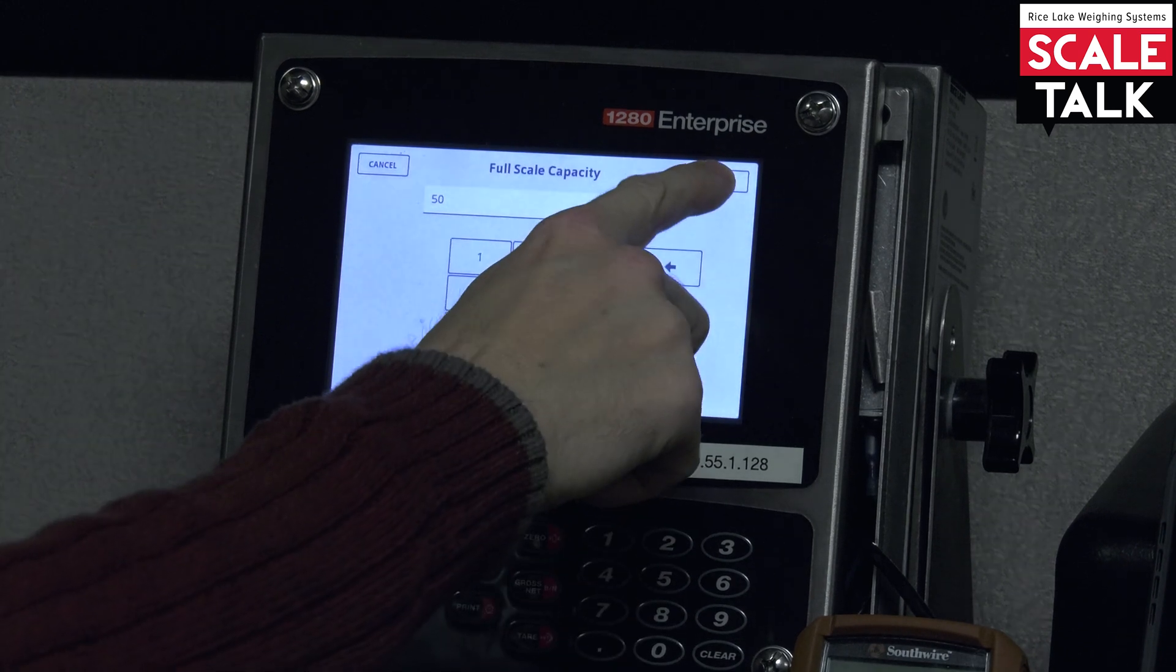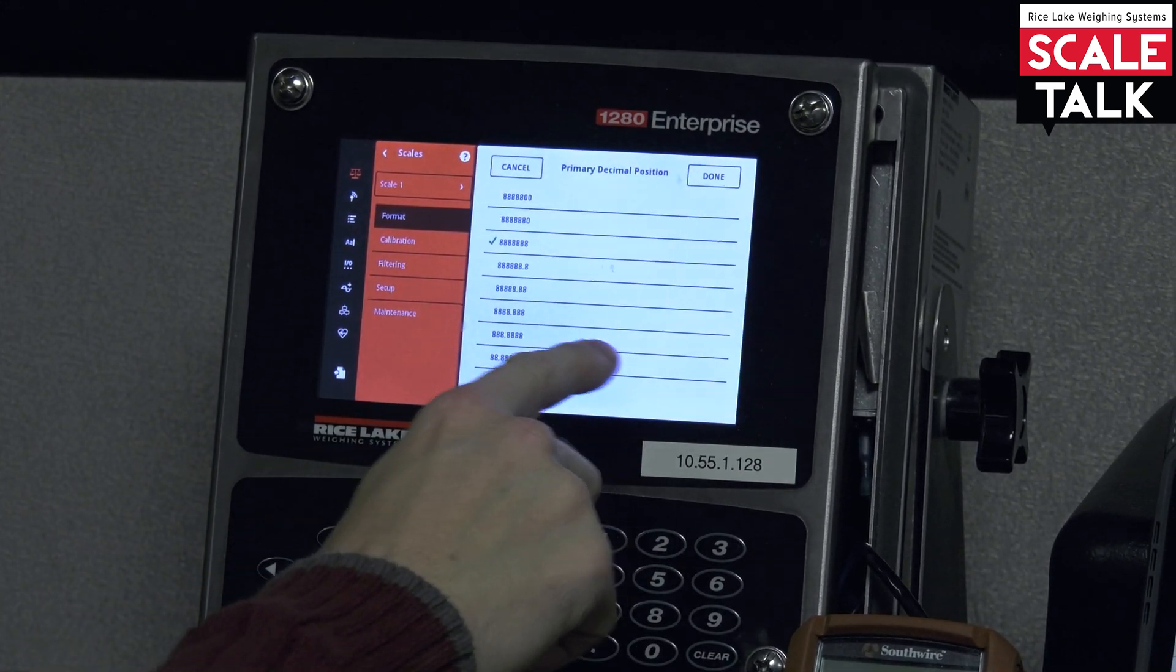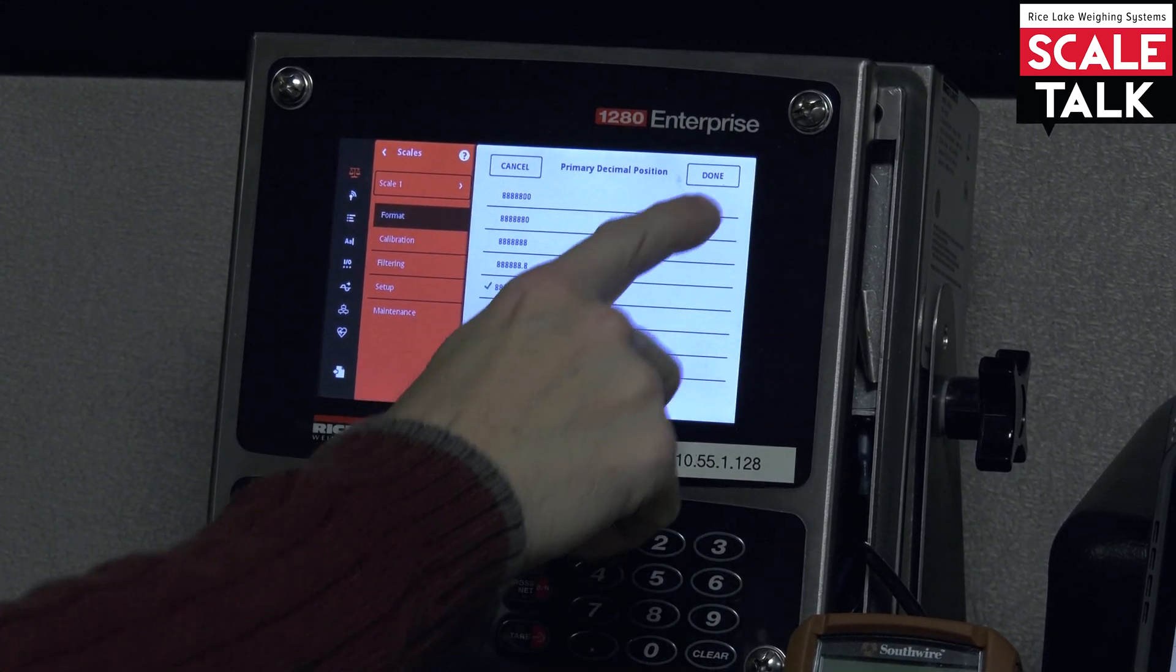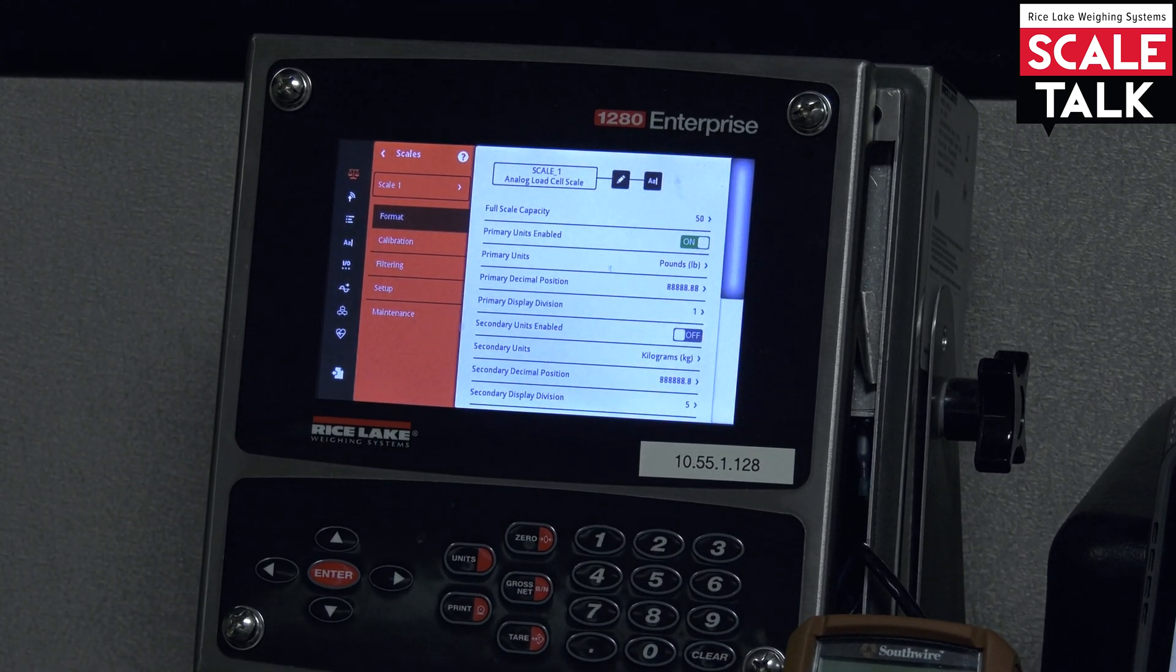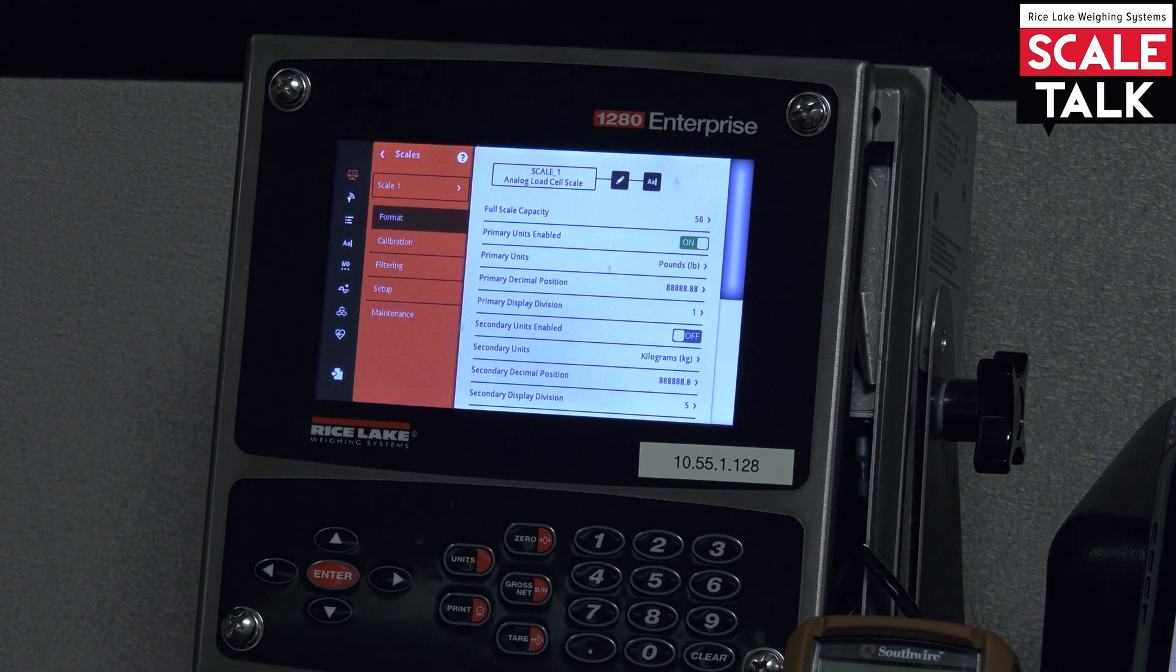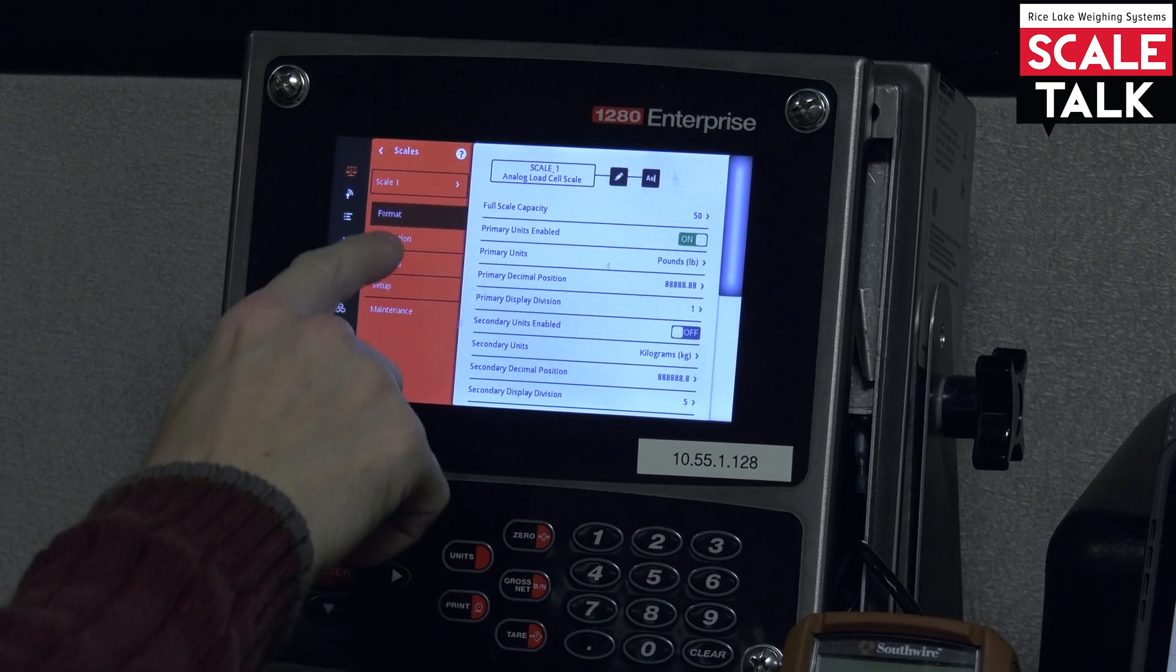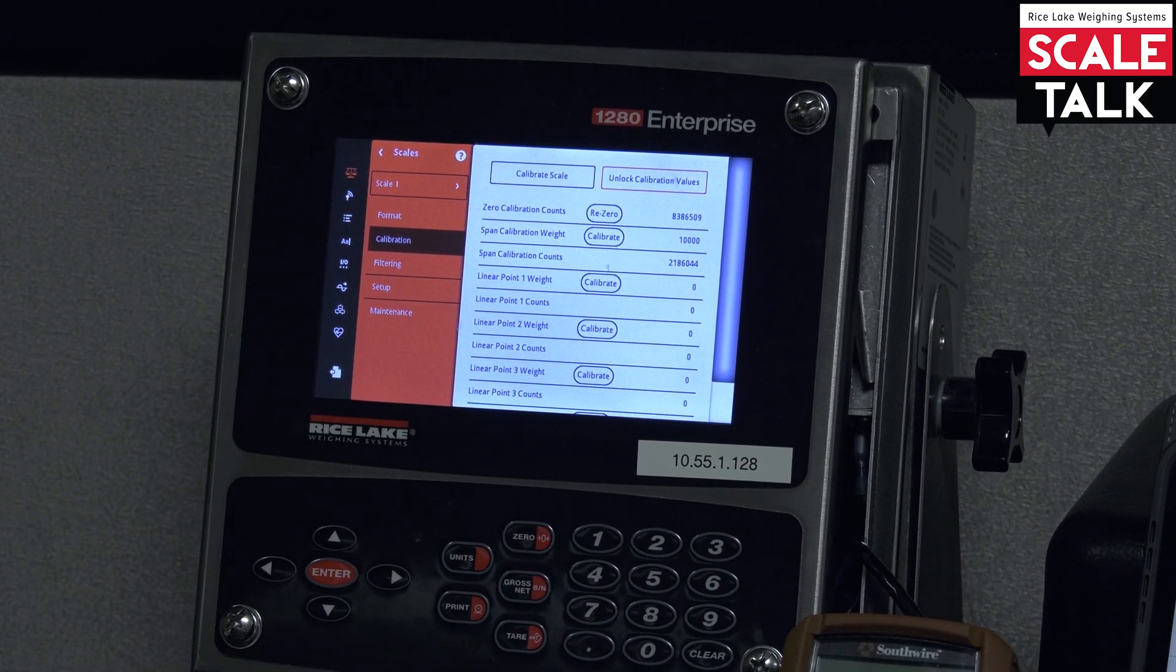I'm going to set it up to be 50 pounds and we're going to set it up to count by 0.01 of a pound. So at this point we have that much done. So we'll go on to the calibration portion.